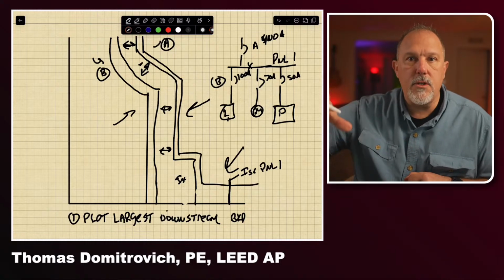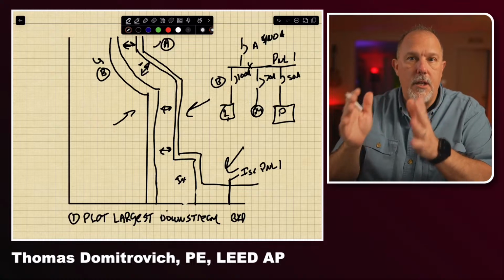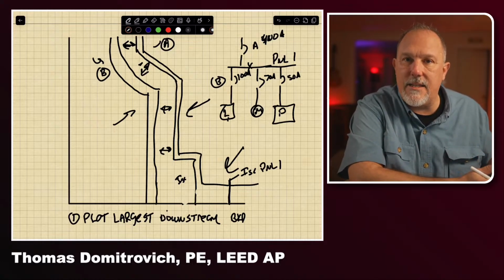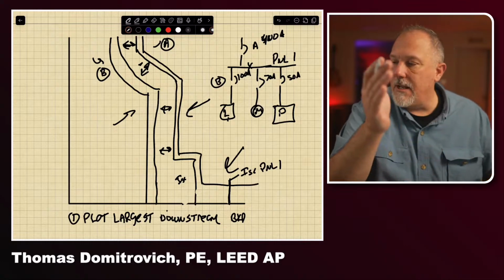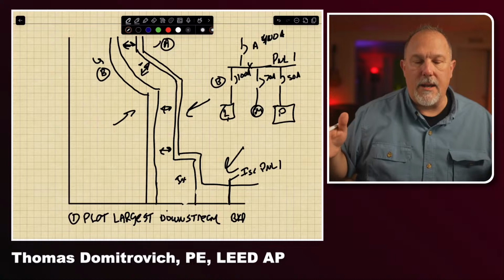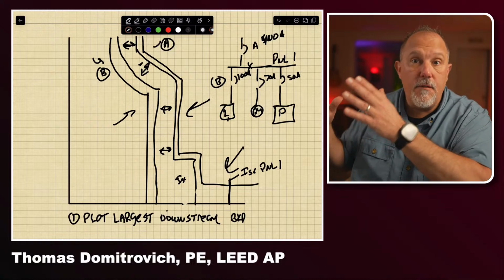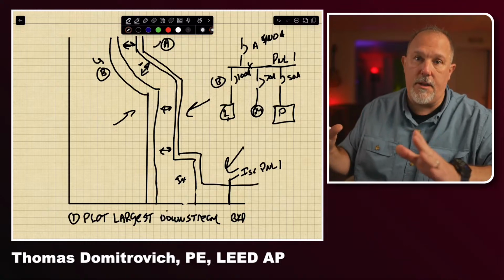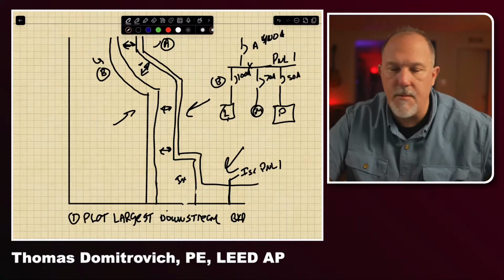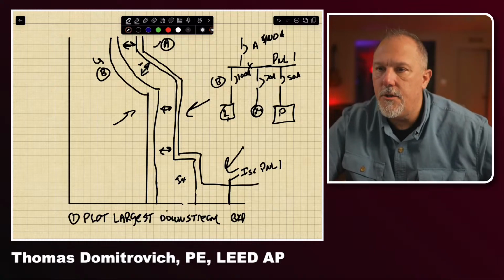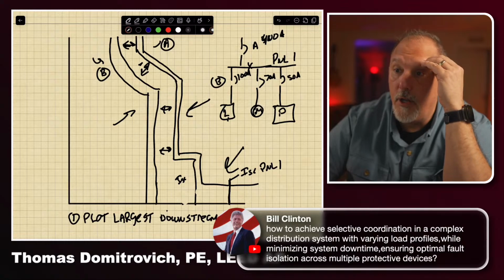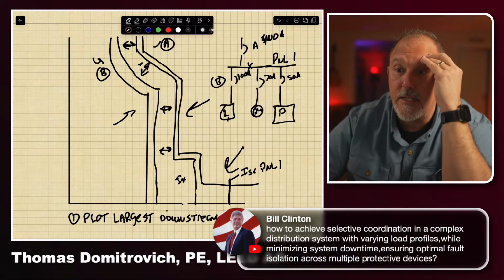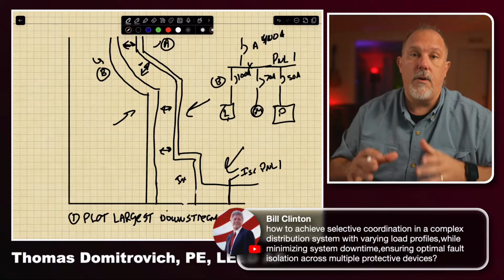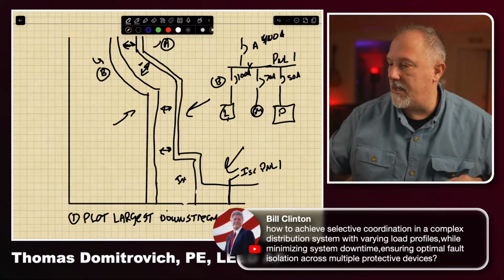So, I don't care necessarily about the loads, because the loads are going to be taken care of: I need to make sure that they're less than the conductor ampere rating and less than the circuit breaker long time pickup. What I care about is the available fault currents, which will change depending upon the configuration of a complex system. So your comment was about load profiles in a complex distribution system. Now, in a complex distribution system, I'm going to want to calculate my fault current. So let's do this, Bill.